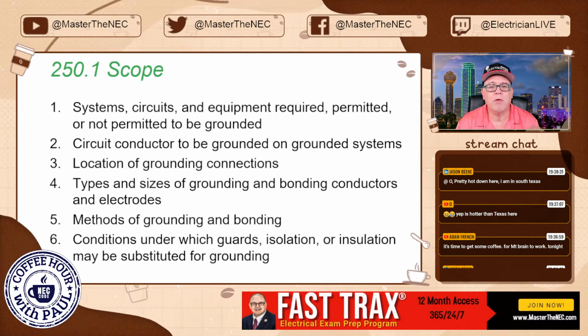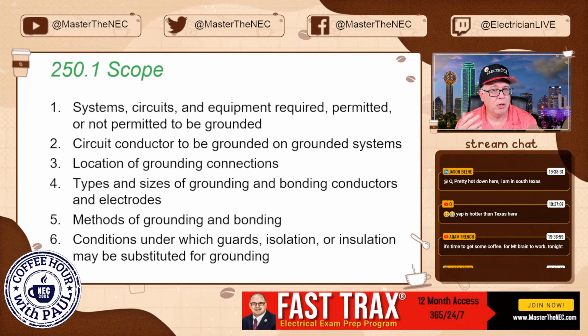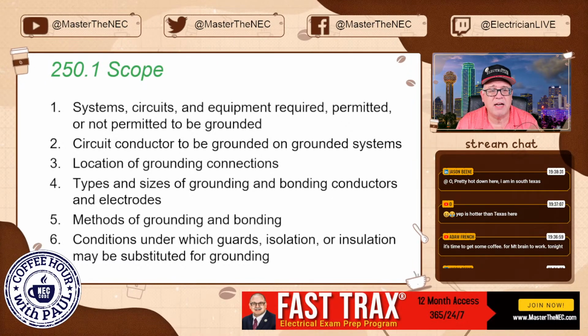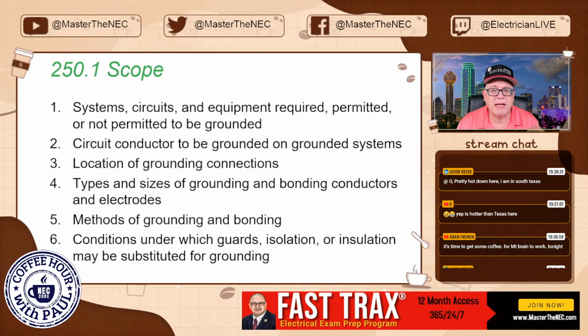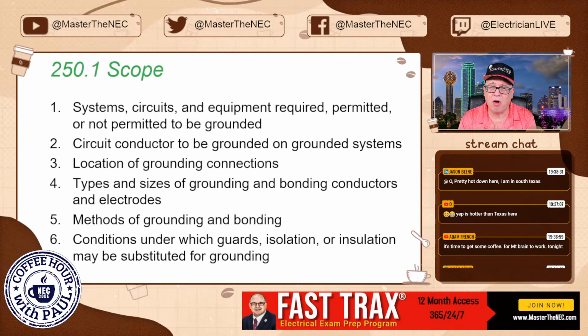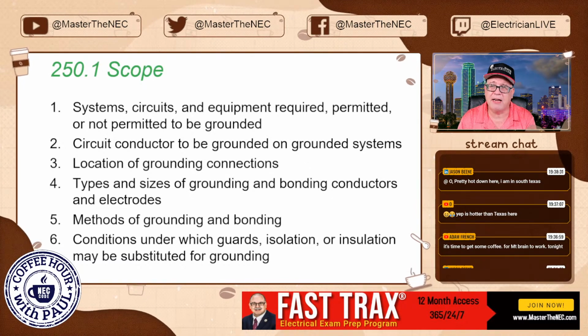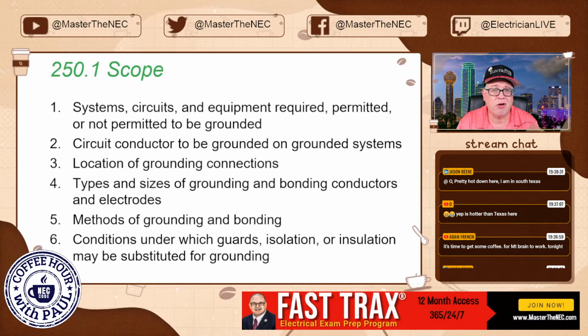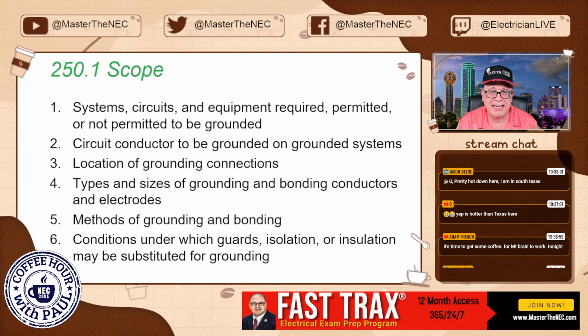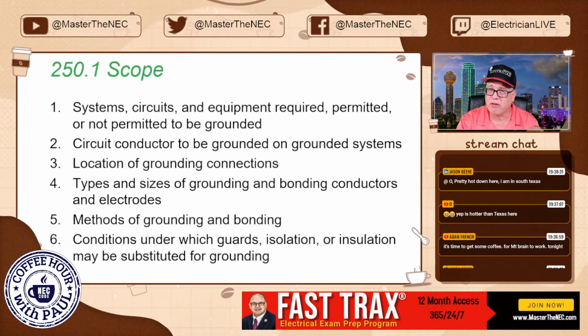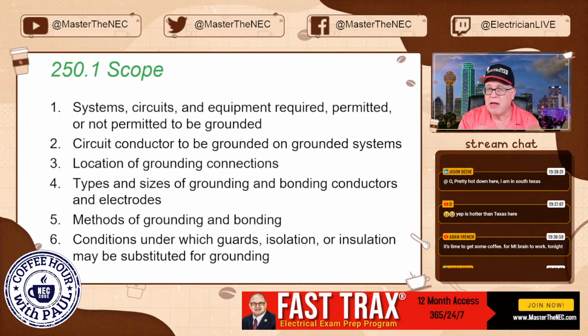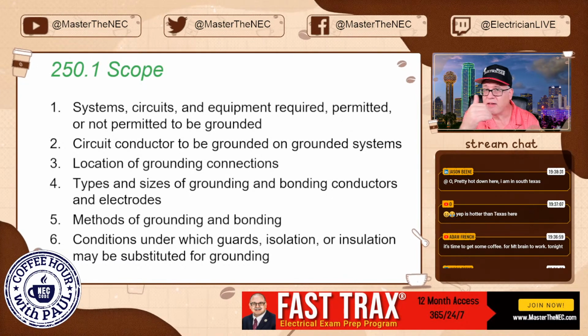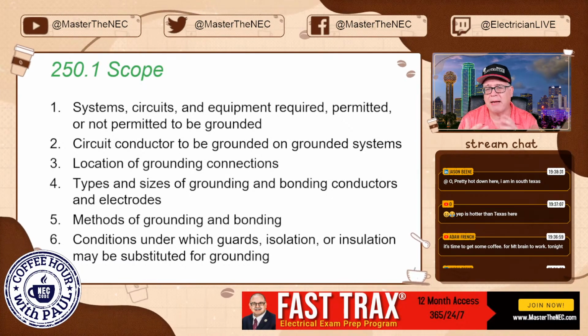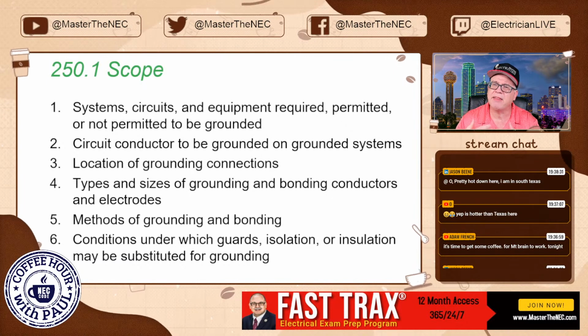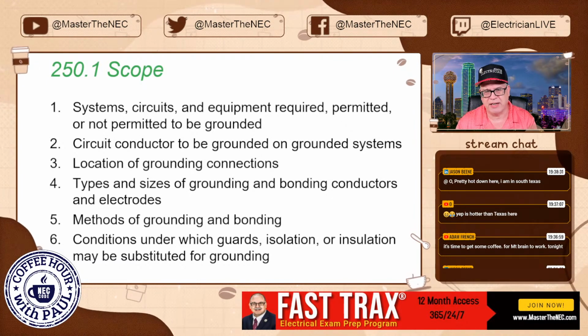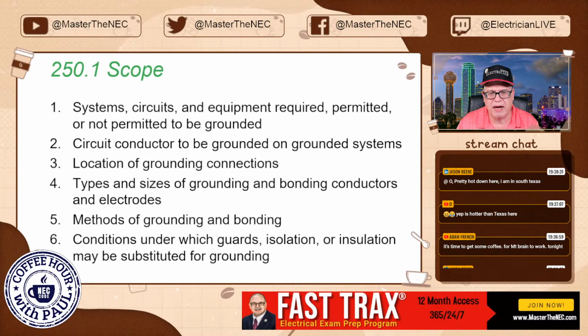Right. The location of grounding connections. That's covered in the scope of 250, obviously. Types and sizes of grounding and bonding conductors and electrodes. Y'all are probably well familiar. If you've been watching me for any time, you know that we talk about grounding electrodes in 250.50. They all get tied together. Then you start getting the list of the electrodes in 250.52, A1, A2, A3, A4, A5, A6, A7, A8. You start getting this list of the different types of electrodes. And then we get the methods of how you connect these electrodes. All that's covered in Article 250, obviously.